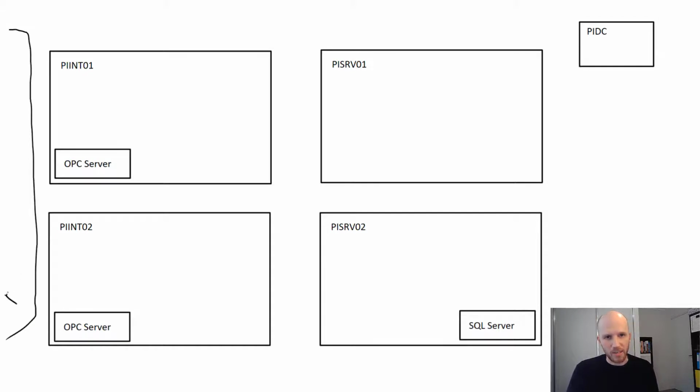We have something like a DCS maybe, a distributed control system. Now we need to read from this in some way using our different PI System components. And generally we need to read from it when it's exposing its data using a certain standard. So this DCS is hooked up to all of our sensors, etc., and it's exposing its data to other systems using these things called OPC servers. So in our case here, we're assuming that we have redundant OPC servers, so 2 of them with exactly the same data. All of the sensors on our plant are exposed using this OPC standard.